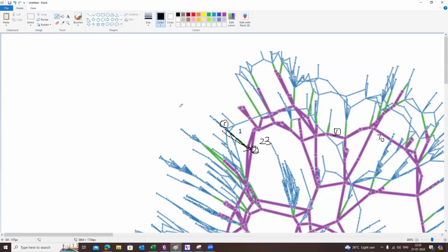The 90 degrees I am talking about is this: let's suppose this bus is at 1 degree, for example, and this bus 70's angle is something like 85 degrees. From this bus to this bus in the interconnected system, the angular difference is almost 90. If it crosses 90, there will be uncontrollable power flow from this bus to this bus.